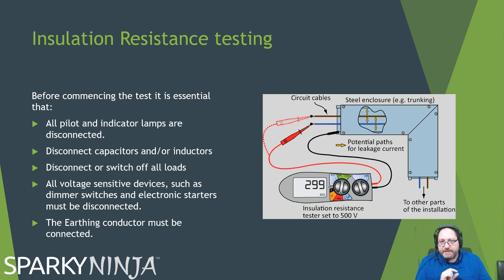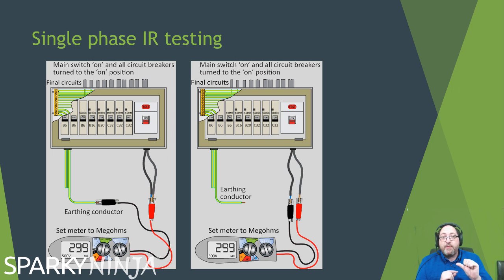Now there are a couple of ways you can do this. If you're working on a single phase board, this is the way it's illustrated here. Main switch on, circuit breakers on, all of them, equipment out, and they've connected to the supply tails coming in. Now if your supply tails are going into a service head or a meter, then you're not going to be able to do that. So the thing that you do differently is your main switch would be off, and you'll go to the supply side, the load side of the main switch, the isolated side of the main switch. If you can't take the tails out, fine. Main switch off, locked off, and test on the load side, the dead side of the main switch. But the MCBs and breakers must all be in the on position. If they're in the off, then you're going to get a good reading because you're testing absolutely nothing. So you must be testing something.